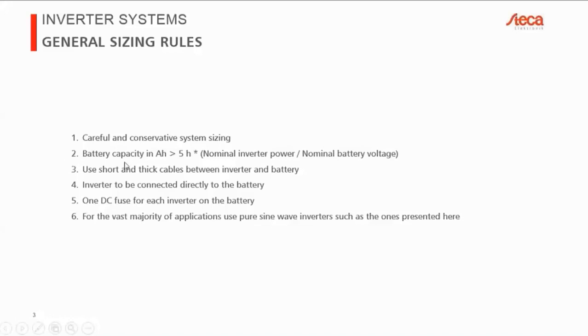The second point is the battery capacity. This is a common question. What battery capacity should be chosen? Of course, the battery capacity, again, is something that you will find when you're sizing your system because it depends on things like your depth of discharge, on your autonomy, how many days your system can remain autonomous even if there's no recharging at all from PV or from any other energy source.